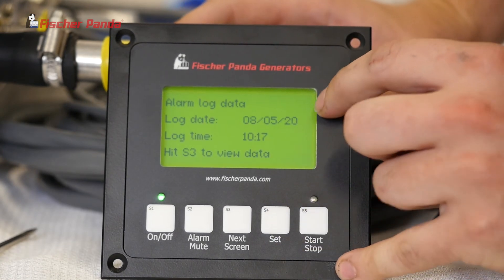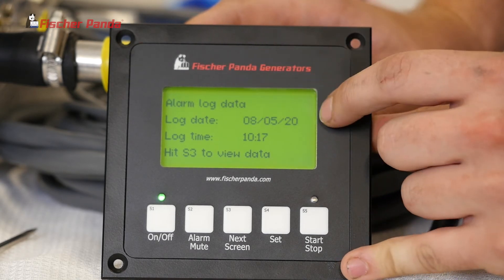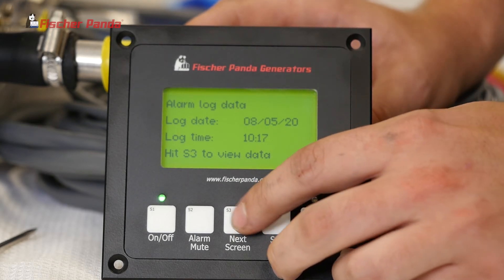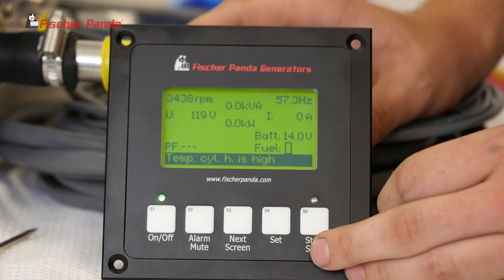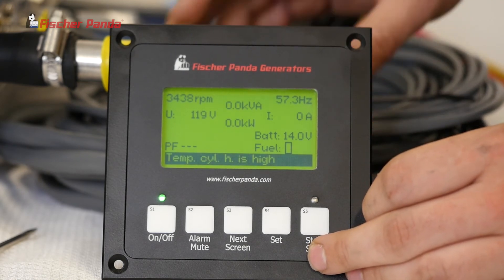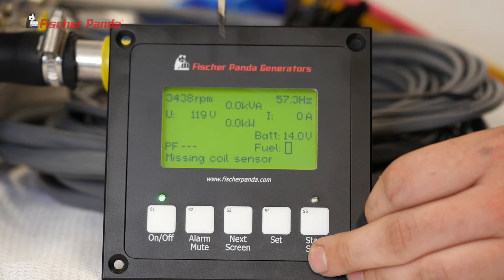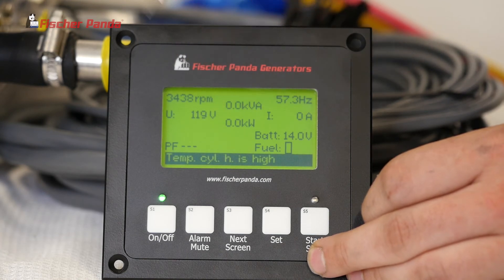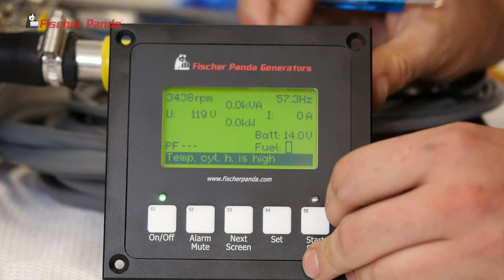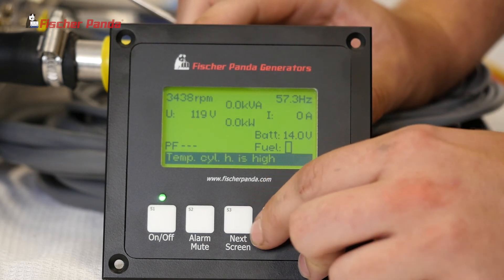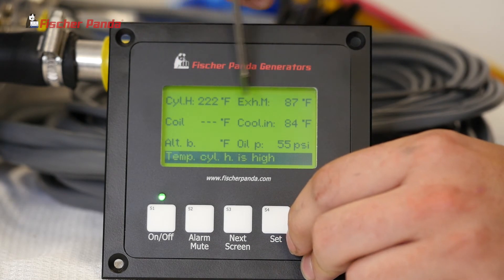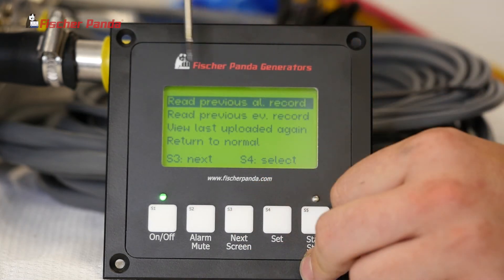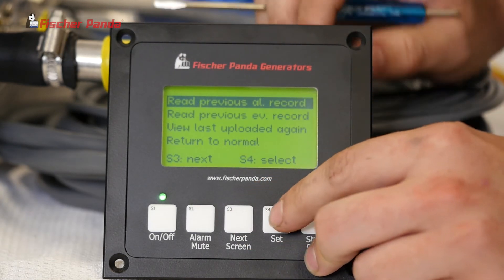From here, select Read Previous Alarm Record and press S4. This will show the most current alarm you have. The first screen displays the time the alarm occurred and the date. Press S3 to view it. The last alarm for this unit was a high cylinder head temperature. You can see all the parameters at shutdown: engine speed, frequency, battery voltage, and output voltage.